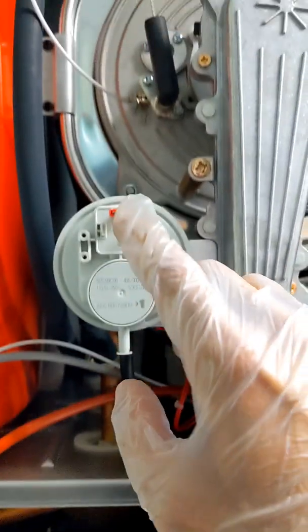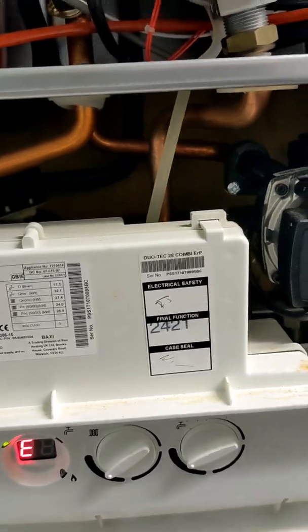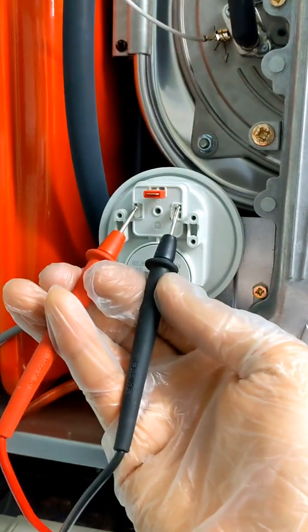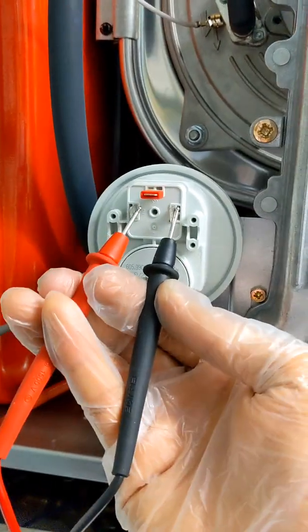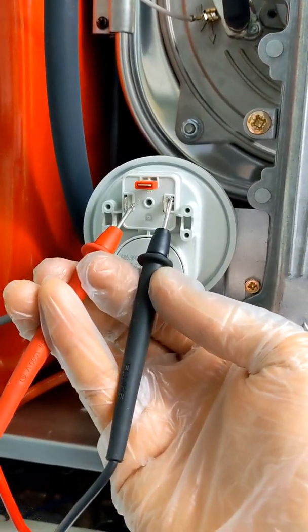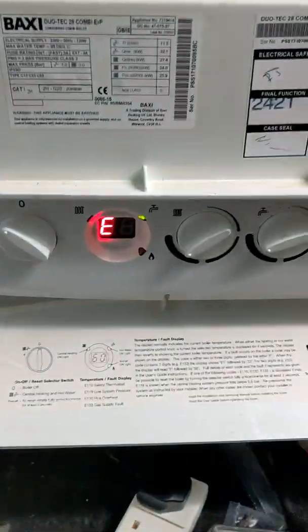That relates to the air pressure switch. At rest, I should have continuity across this. There's no continuity across that, but as soon as I bridge out the connections on the air pressure switch...